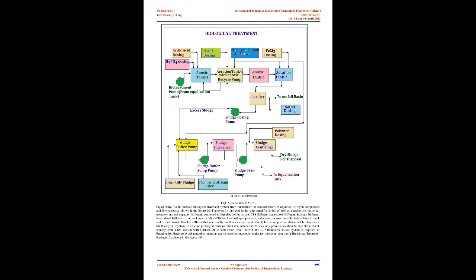One flow transmitter is provided at the outlet of the clarifier to monitor the flow to the outfall basin. One online chlorine analyzer is also provided at the outlet of the clarifier to monitor the free chlorine in clarified water and also to control the stroke of the NaOCl dosing pump.